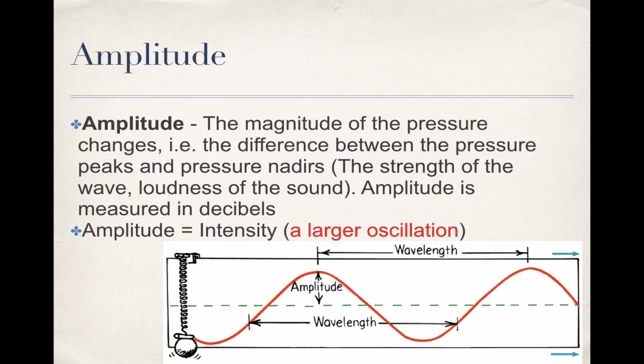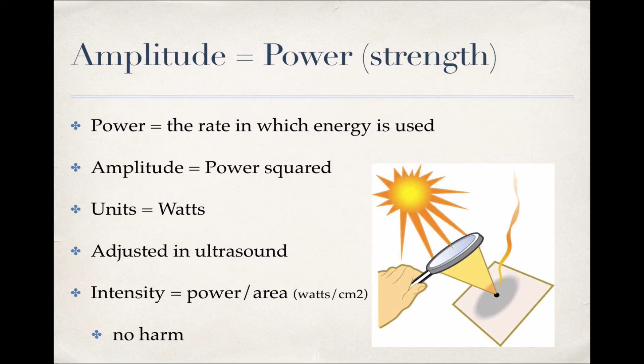So taking the sun and the magnifying glass as an example, if you were to take ultrasound waves or sun waves, electromagnetic waves in this case, and then focus them on a single point, you would take that intense wave and then make it much more powerful on a single point, and then that can light a piece of paper on fire. In the case of ultrasound, that can be targeted to lyse tumors and things like that. So the units for amplitude are watts. And we try to adjust this in ultrasound. There's a lot of safety check marks built into the machine to make sure that the intensity and the power is not high enough to cause harm on your diagnostic ultrasound.